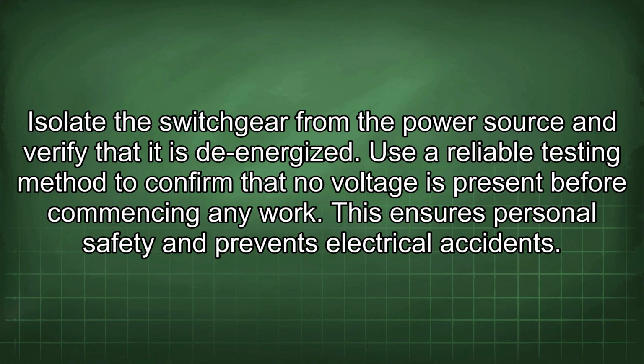Isolate the switchgear from the power source and verify that it is de-energized. Use a reliable testing method to confirm that no voltage is present before commencing any work. This ensures personal safety and prevents electrical accidents.